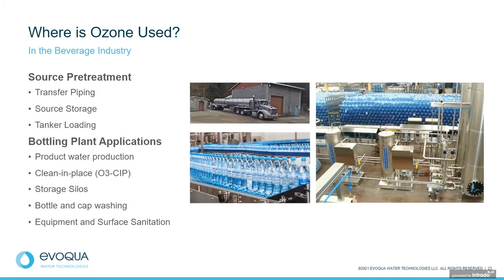Where's ozone used? Hopefully you are using this in all of your potential applications in your facility. Pretreatment at the source, where you could be transferring in the piping, the storage, and even some of you might be getting an offsite source in a tanker, where you can have ozone added to keep it disinfected and disinfect that tanker. Inside of the plant, the applications are the product water, clean in place, if you're not using it, it's an option, the storage silos, bottle and cap washing, and the equipment and surface of that equipment being sanitized.